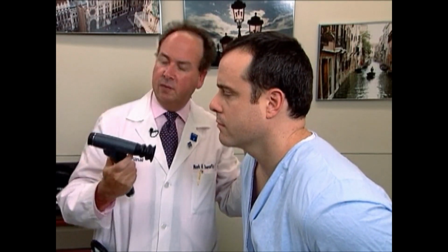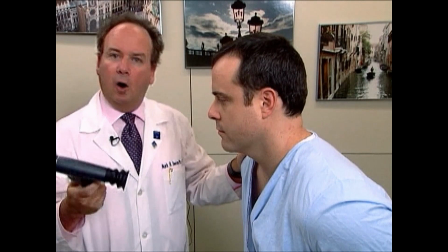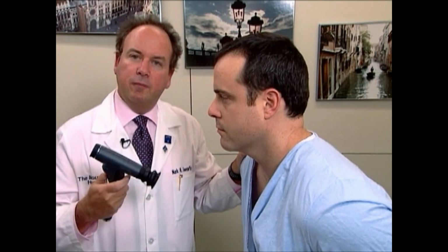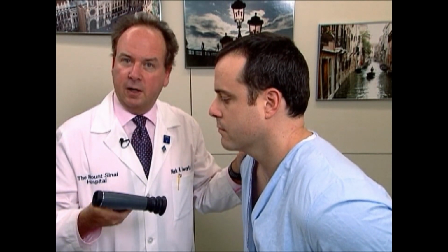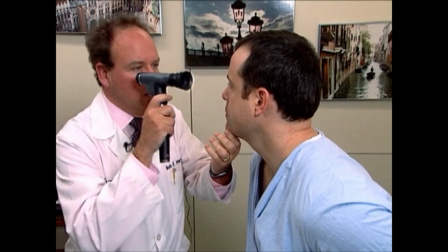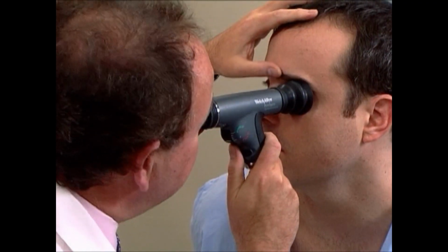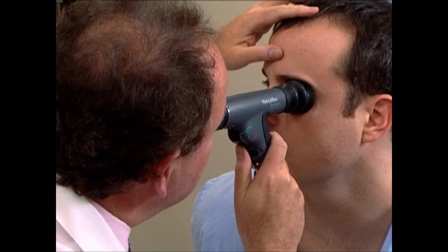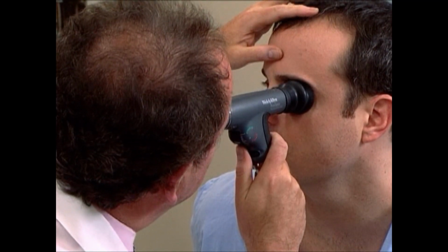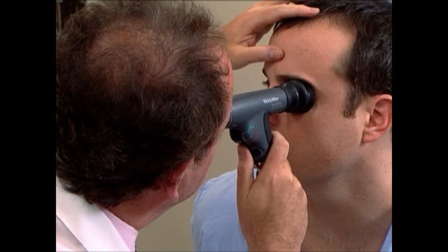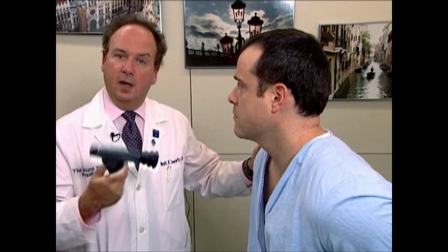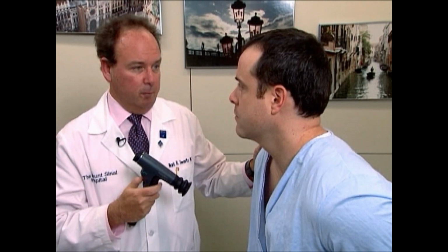A major advantage of this is that many individuals are one-eye dominant, and therefore may have trouble using their left eye to examine the left eye of the patient. With the panoptic, if you just turn this way, Mr. Johnson, and look straight in the distance, I can actually visualize Mr. Johnson's left retina by using my right eye, as I'm demonstrating now. In addition, of course, I could use the instrument in my left hand and examine the left retina as well.